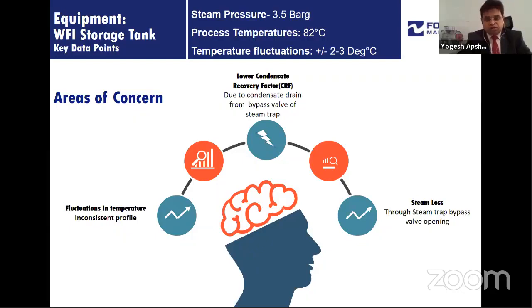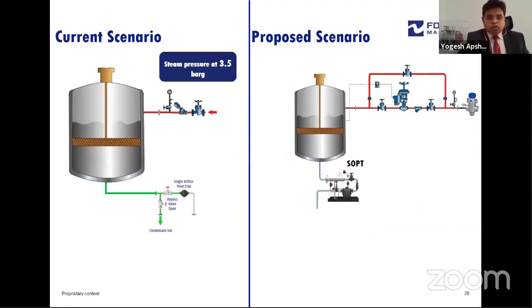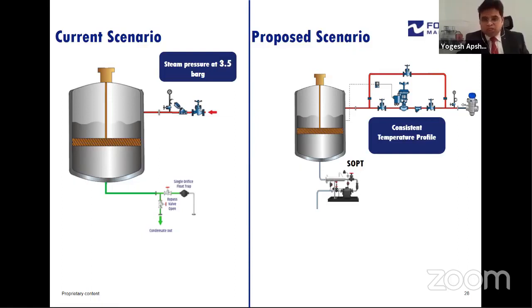Also, the lower condensate recovery factors. In the startup, the condensate or the steam loads are quite high. As the temperature starts achieving, the consumption of steam in the WFI storage tanks starts tapering, and there are steam losses also to the bypass valves. So this is what we have observed in typical plants, and what we have recommended is a PID based temperature control system, which will maintain a consistent temperature of the WFI at 82 degrees Celsius or 85 degrees Celsius with a plus or minus 1 degree Celsius.